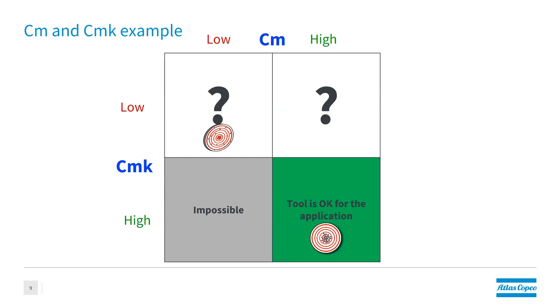Think about it a little, and I'll tell you the answer: the tool is good in the end. Having high repeatability is really a characteristic of the tool - you cannot change its nature to make it more or less repeatable. If a tool starts with low repeatability, you can do whatever you want to it, but if it was designed that way, you cannot change its nature.